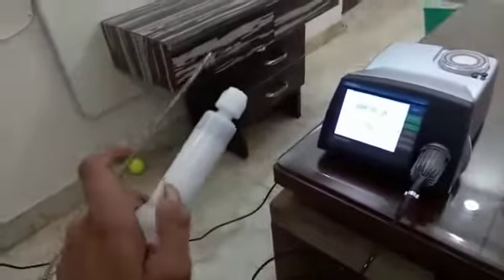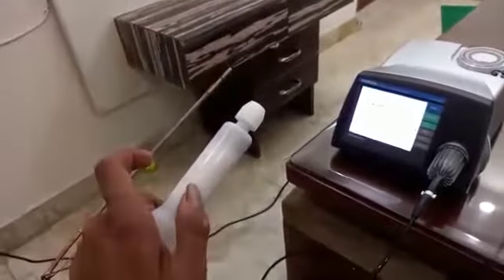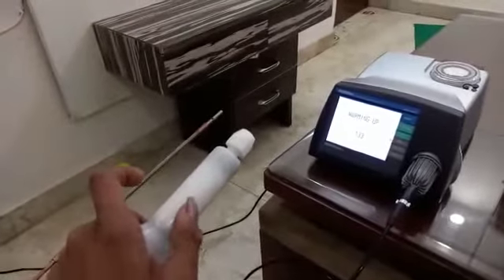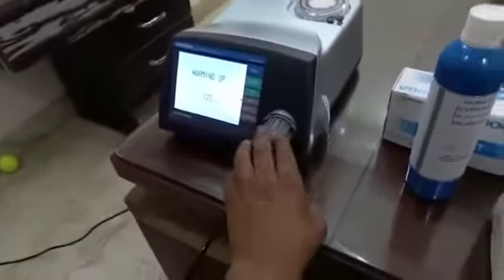Along with that, I'm just showing some more things, like this is the dust filter. Whenever the sample enters the analyzer, before the final bench, this dust filter is used to filter the final emission. What I mean to say is, this is the initial filter. It has a filter inside. So after the sample passes this, it goes through this channel via this sampling pipe through the drain separator, and after that it enters the Mexa.